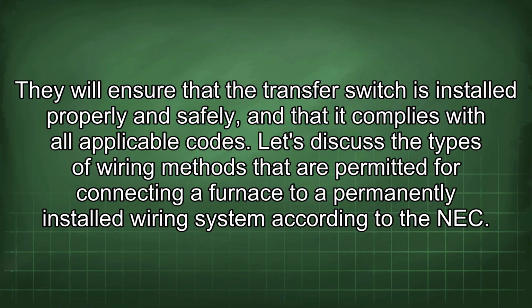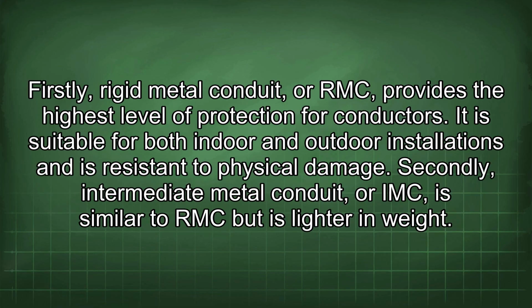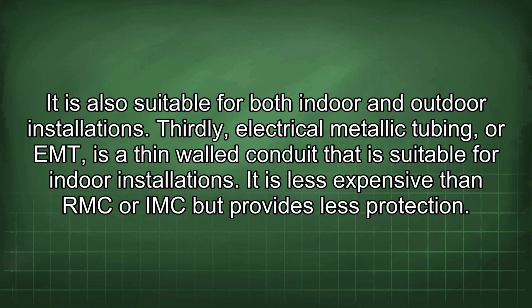Let's discuss the types of wiring methods that are permitted for connecting a furnace to a permanently installed wiring system according to the NEC. Firstly, rigid metal conduit, or RMC, provides the highest level of protection for conductors. It is suitable for both indoor and outdoor installations and is resistant to physical damage. Secondly, intermediate metal conduit, or IMC, is similar to RMC but is lighter in weight. It is also suitable for both indoor and outdoor installations.